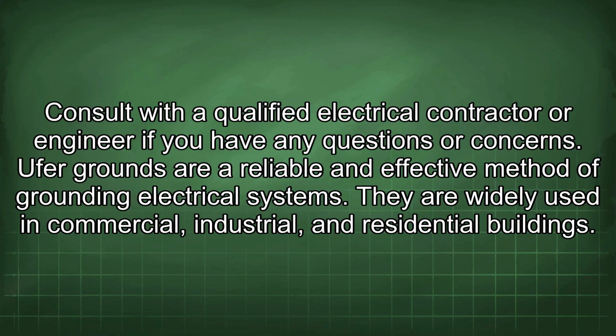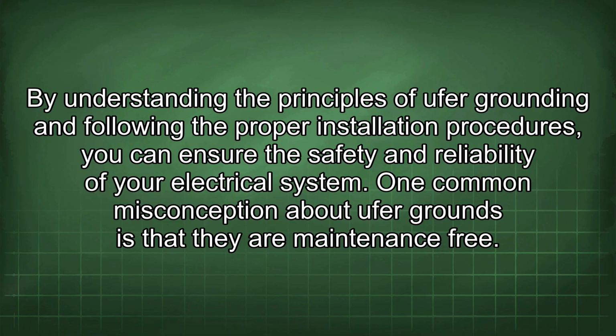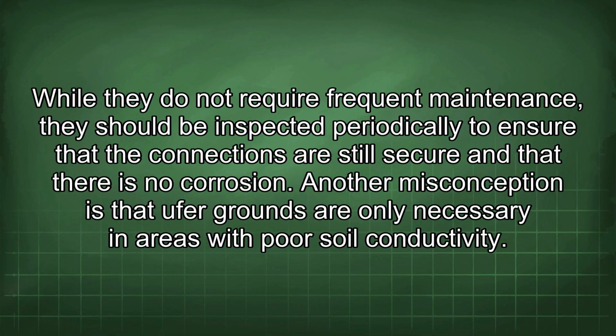Ufer grounds are a reliable and effective method of grounding electrical systems. They are widely used in commercial, industrial, and residential buildings. By understanding the principles of Ufer grounding and following the proper installation procedures, you can ensure the safety and reliability of your electrical system. One common misconception about Ufer grounds is that they are maintenance-free. While they do not require frequent maintenance, they should be inspected periodically to ensure that the connections are still secure and that there is no corrosion.